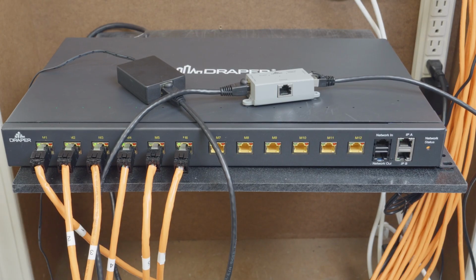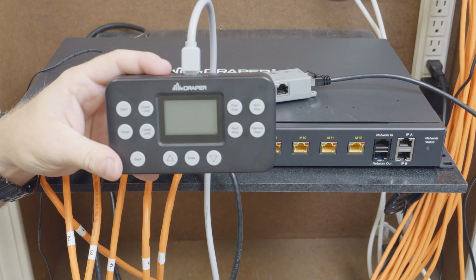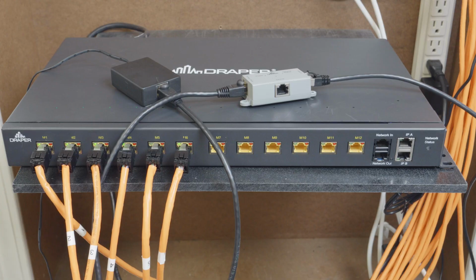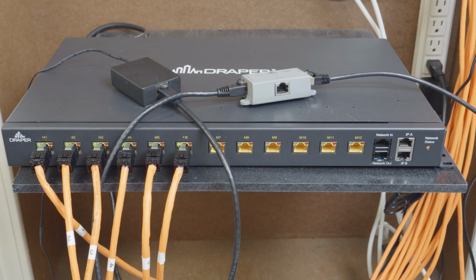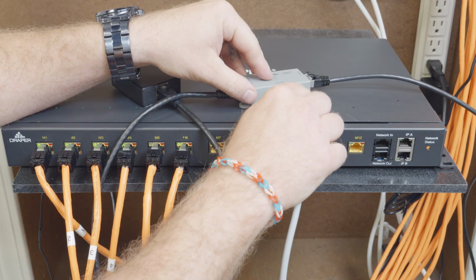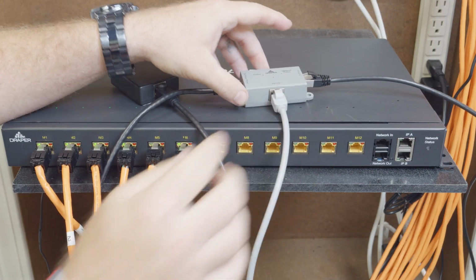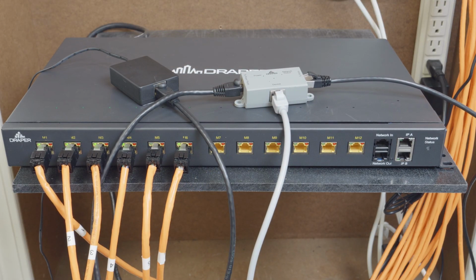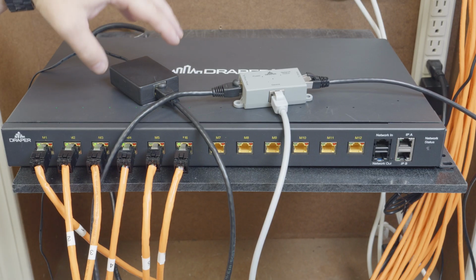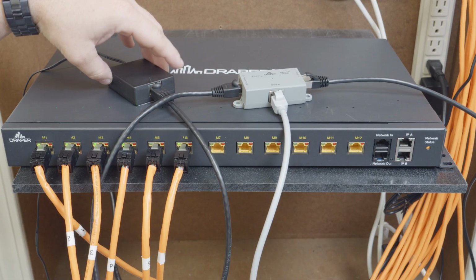And then for programming purposes, you will need your motor limit tool. So I'm going to take that, and now I will plug that into the device port of the low voltage MDC. We now have a temporary power supply for this single motor. I can now program my limits, set my groups, and then walk away until the electrician has the final wiring in place.